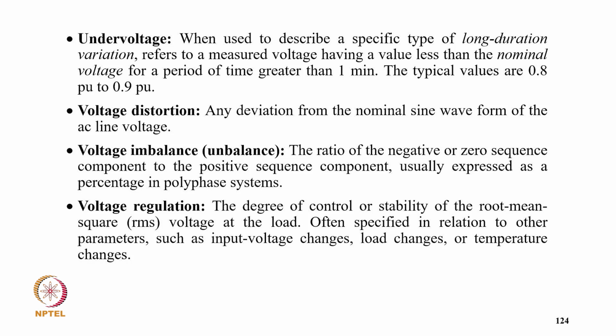Voltage distortion: deviation from the nominal sine wave form of the AC line voltage. Voltage imbalance: the ratio of the negative or zero sequence component to the positive sequence component, usually expressed as a percentage, in a polyphase system. Voltage regulation: the degree of control or stability of root mean square voltage at the load, often specified in relation to other parameters such as input voltage changes and load changes.